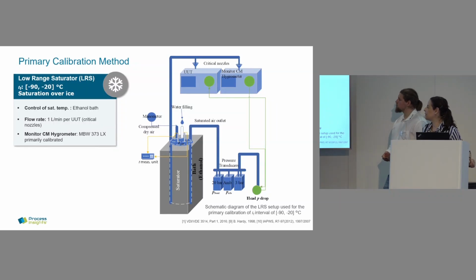What is important here, of course, if you want to be traceable to SI, you need to measure something. We are measuring temperature, so inside here, sorry, this is my not so good representation, we have two PRTs, platinum resistance thermometers, crossing the saturator. And we also need to measure pressure, of course: the pressure at the outlet of the saturator, with a 20 bar transducer, the ambient pressure, and also the pressure drop at the unit under test.